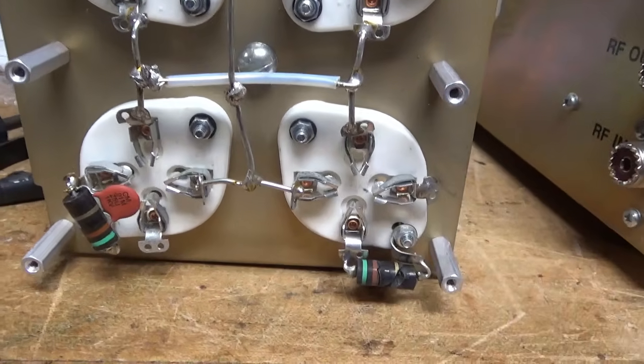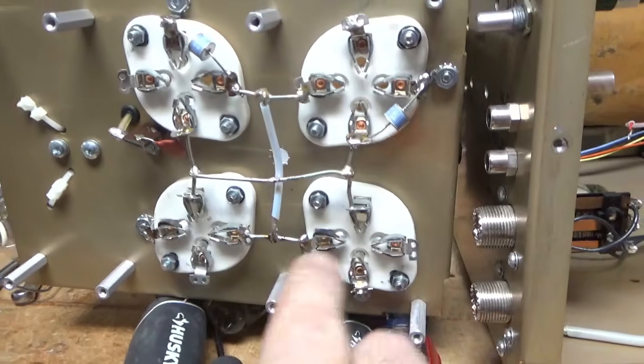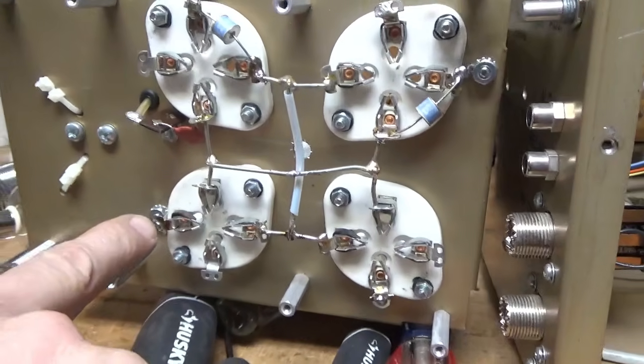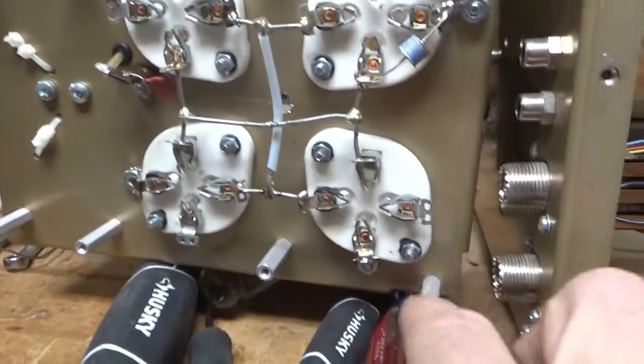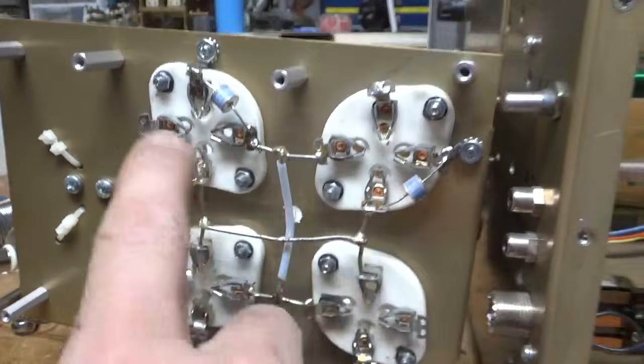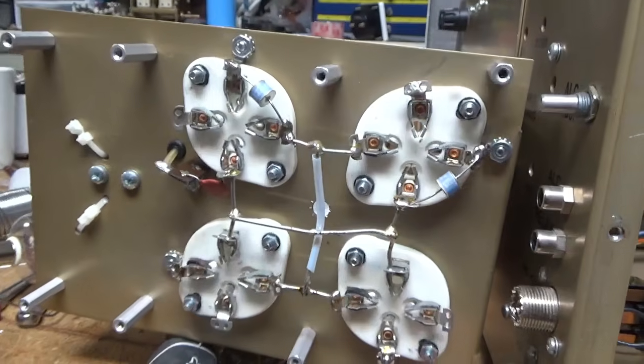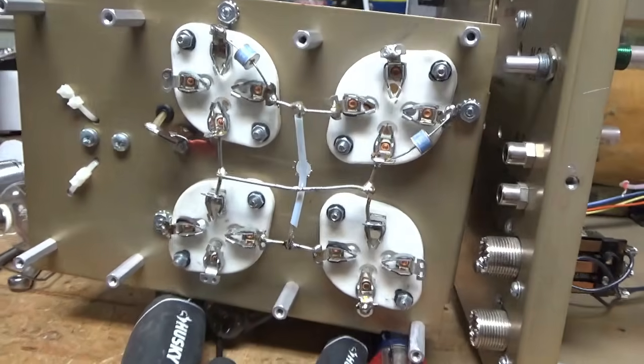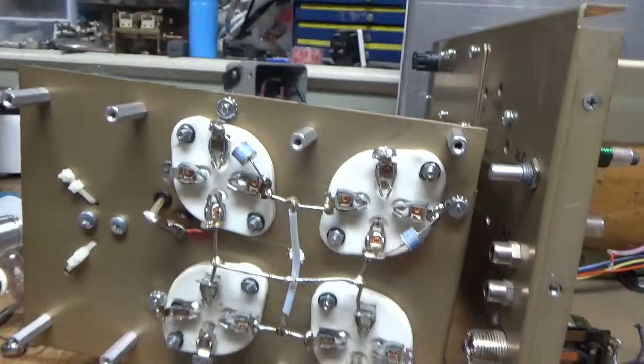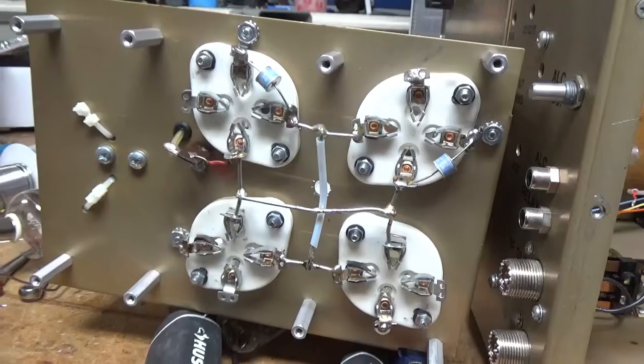See you soon. I replaced the clips on two of the sockets, grounded the grid connection for each socket directly to the metal, added the two gas discharge tubes, compressed the socket clips and cleaned them, and tightened all these standoffs - they were loose. Okay, I'm going to get back to work.